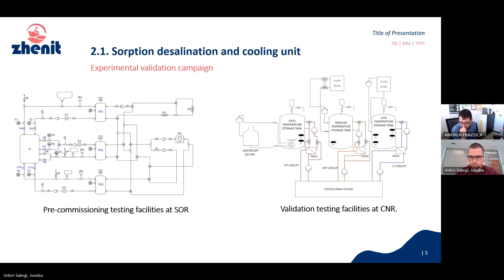These are the conditions we tested so far. As you can see, we are driving the process at 85 degrees C, which is more or less the temperature that we can expect as waste heat on board of the vessel. We are providing cooling at 15 degrees C, so basically for distribution with fan coils on board. And we are rejecting it to the ambient at 30 degrees C or 35.